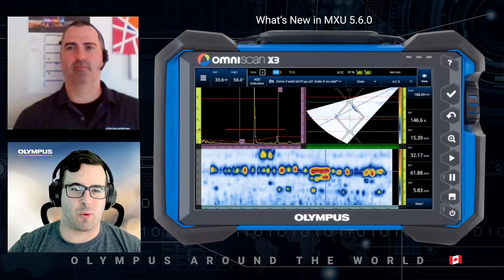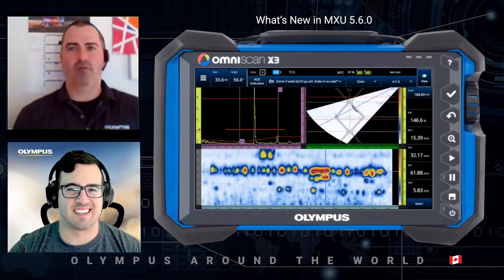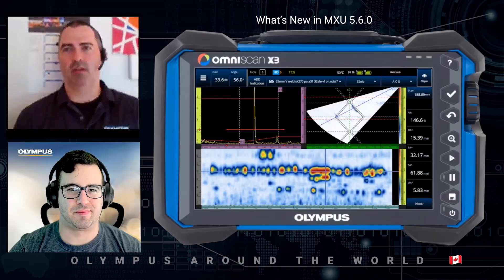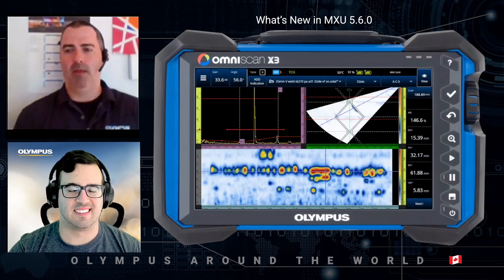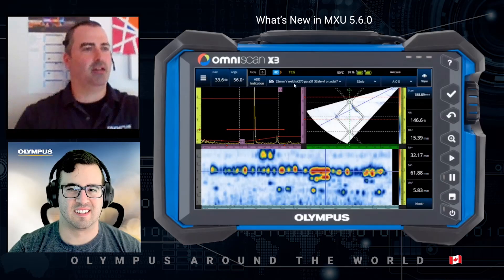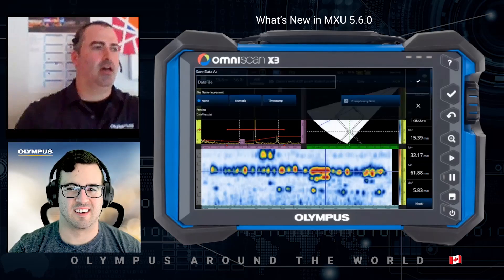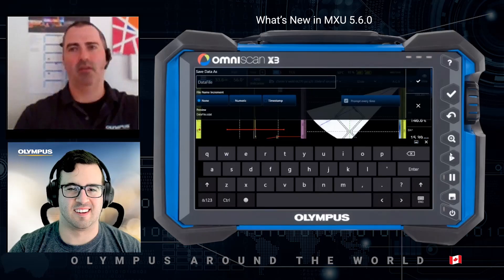Now I'll let Stéphane explain the new saving workflow. With the X3 we received a lot of comments from customers regarding the data file saving workflow, so we heard you and we acted. I will present the new data file saving manager. I have an acquired data file and I'm currently in analysis mode. When I press the Save key on the front face of the instrument, I am prompted with the data file saving manager.